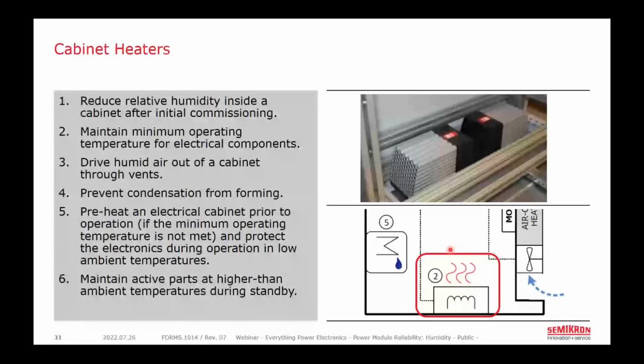But if the outside environment is still humid, you can still be bringing moisture into the system, and your best hope is that by running these heaters, you'll just keep the relative humidity low, even if the absolute humidity is still high. Generally, during system operation, the losses in components, conductors, inductors, capacitors, etc., are high enough to keep the internal components in here above the dew point. But in the event of a low load or standby condition, these heaters can be used.